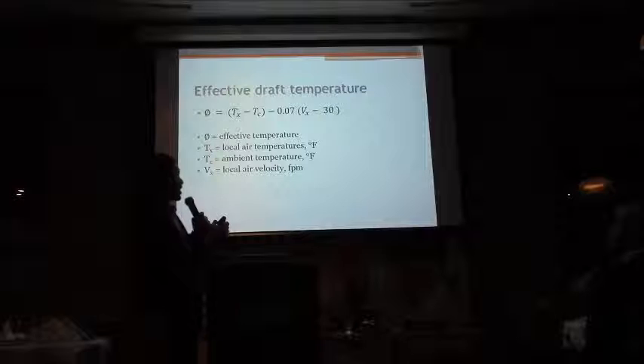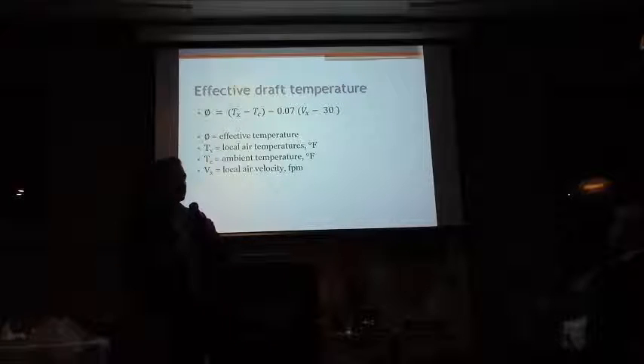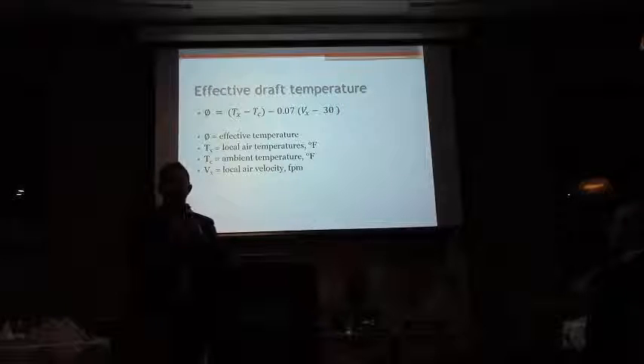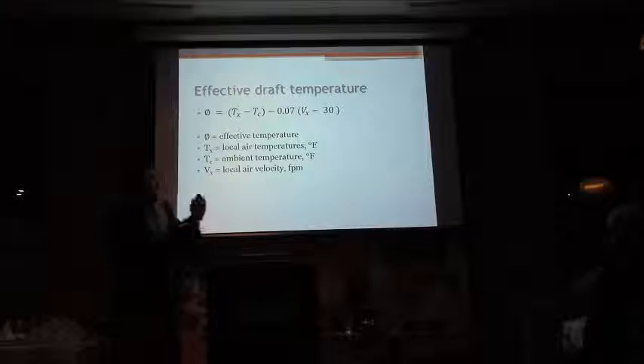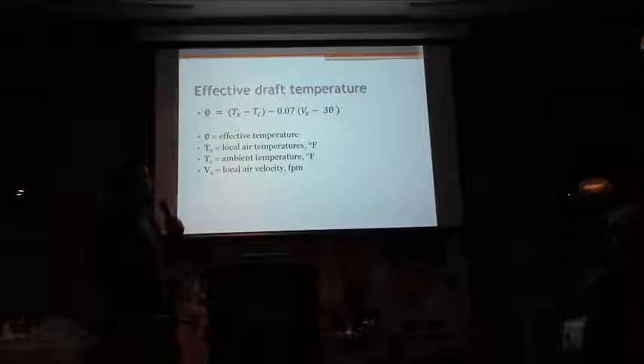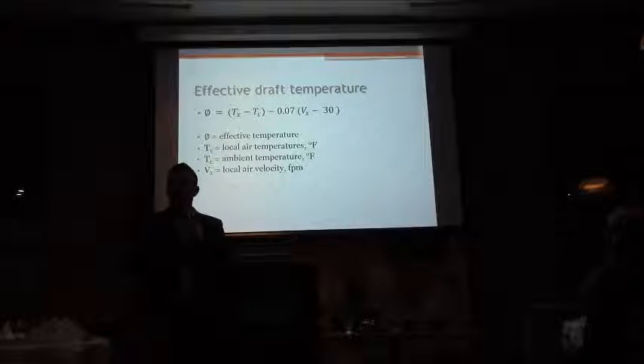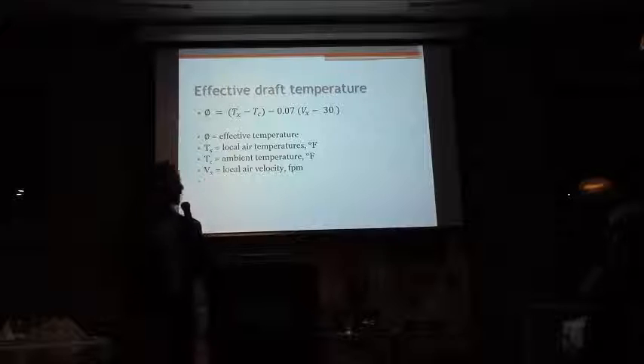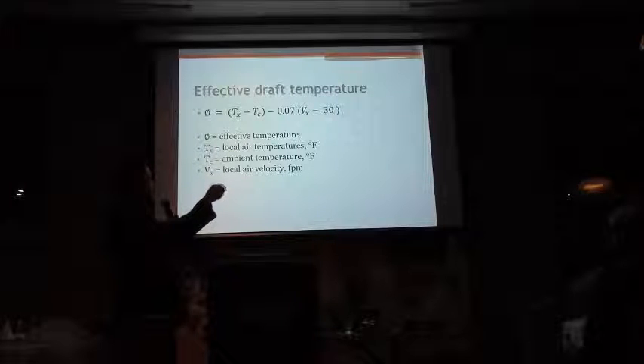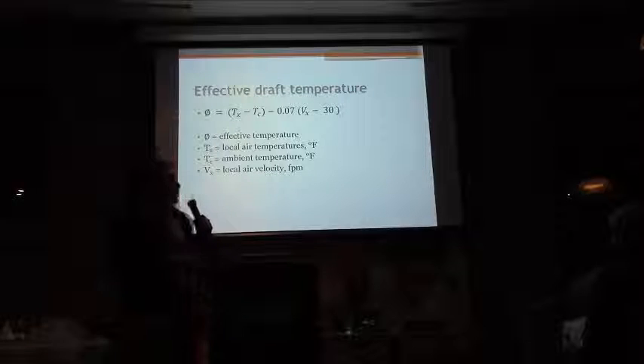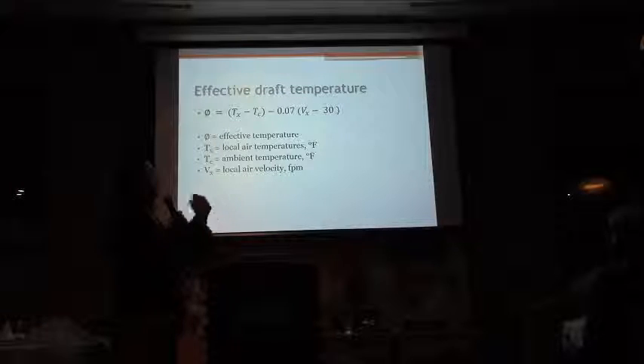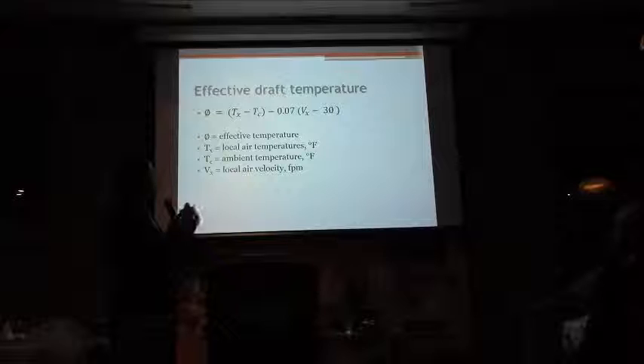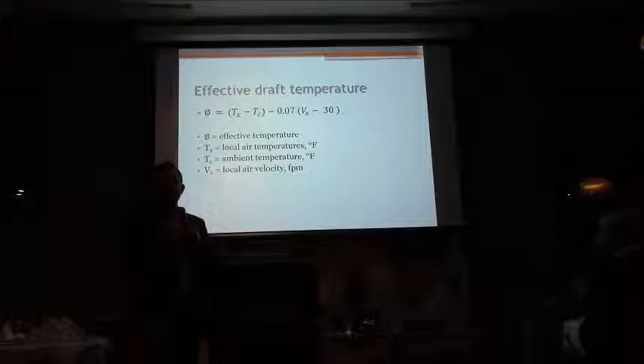And with the effective draft temperature, what it is basically, it's kind of the wind chill factor when you're watching the Weather Network. You know when they say it's minus 10, but it feels like minus 20? This is exactly what the effective draft temperature is. It tells you the effect of air velocity on your body. And if you notice this side of the formula here, Vx is subtracted from 30. So any velocity, in fact, over 30 feet per minute contributes to the feeling of coolness.